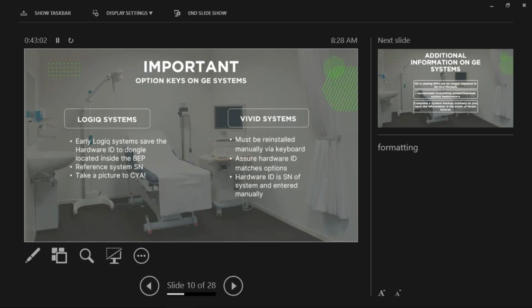A couple other cool features on this particular system. You can run a basic system test on this ultrasound device. It's going to ask me to unplug the transducers. This is just a pass or fail test, but if you run it and the system passes, you can have a pretty high confidence that the hardware in this particular device is good. All of their diagnostic testing for their newer consoles is pretty good. It's pretty spot on. If there's an issue, it will tell you.